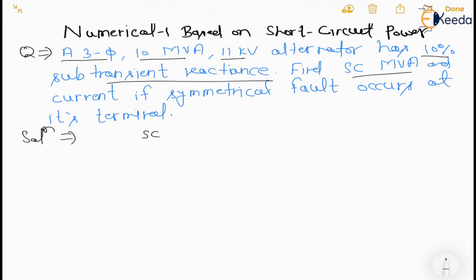So we can easily find out short circuit MVA. We know that base MVA into one upon ZPU. Always remember if the base is not specified then we can take the generator rating as base voltage and base power.